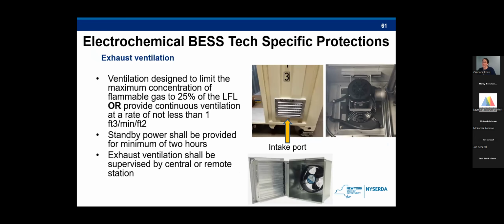So the first requirement here is for exhaust ventilation. So this is required for rooms, areas, and walk-in energy storage units that contain certain electrochemistries. This is not required for lithium ion, but for all other battery types, such as lead acid, batteries are capable of releasing hydrogen gas due to overcharging or other events. So this ventilation requirement is really focused on that. The developer will need to install a ventilation fan for walk-in units with battery chemistries other than lithium ion. The ventilation needs to be designed to limit the maximum concentration of flammable gas to 25% of the lower flammability limit, or provide continuous ventilation.